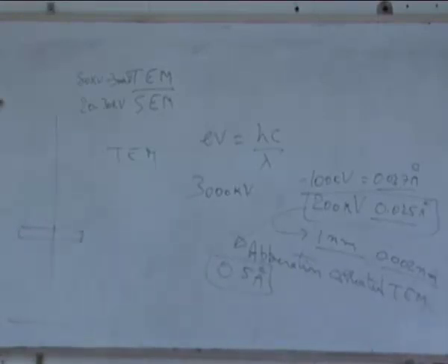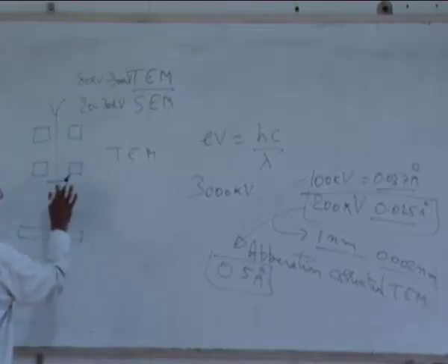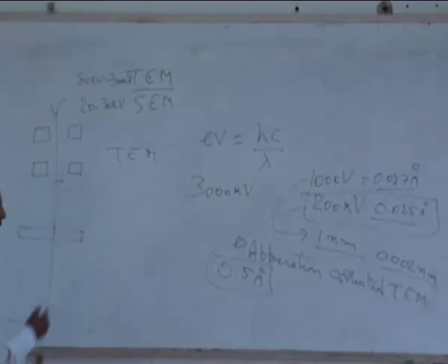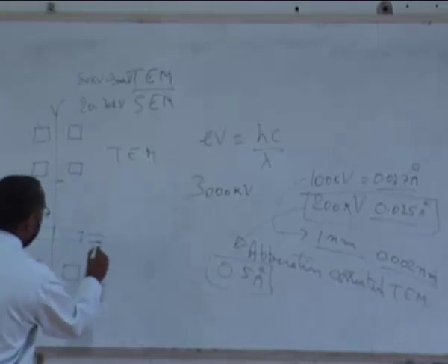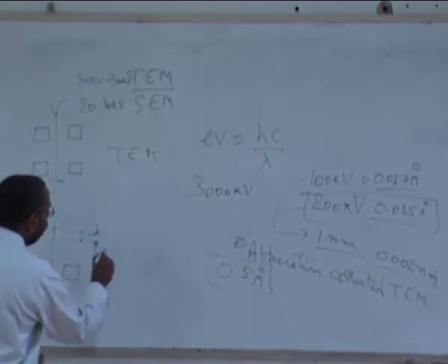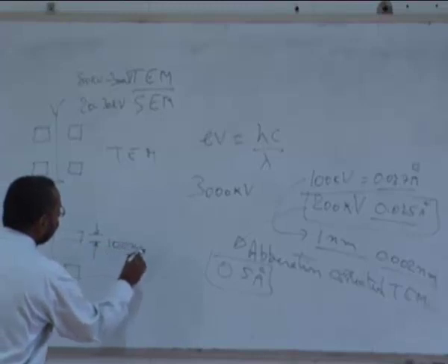Because the electron beam is generated somewhere in an electron gun and goes through certain lenses, you have what are called condenser lenses, you have another what is called an objective lens, and then you have the sample usually kept near the objective lens. Then finally you have also what is called imaging lens, and you have the actual image formed on a screen. And because the electron beam going through the sample has to be very thin, the thickness that we allow is not more than usually about 100 nanometers.